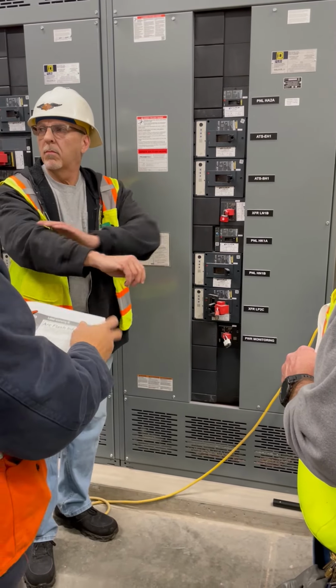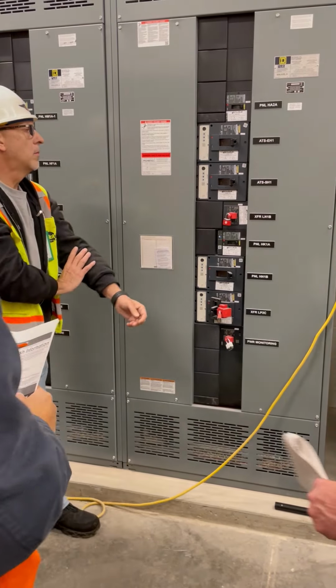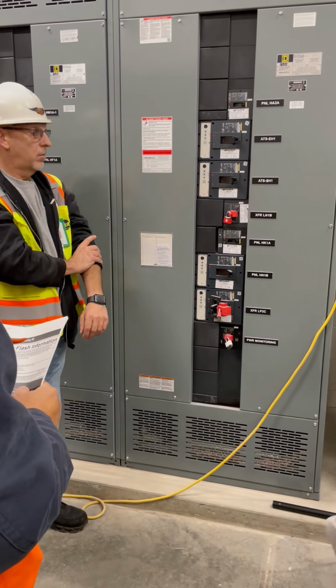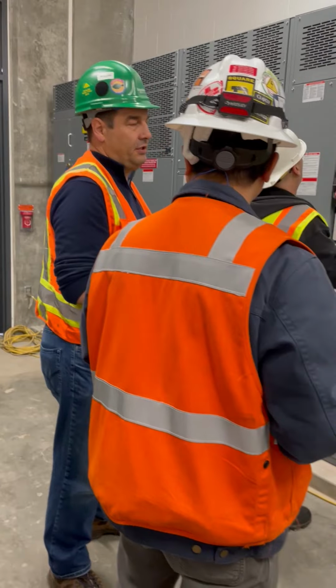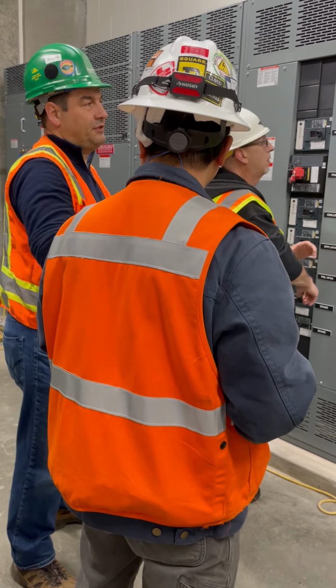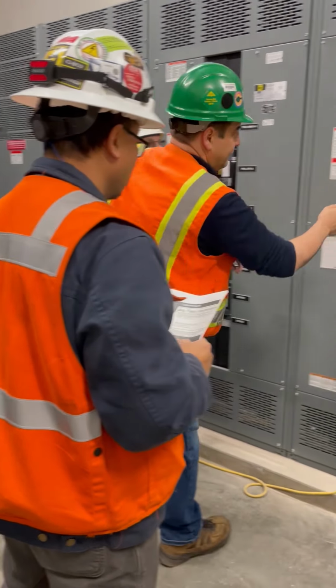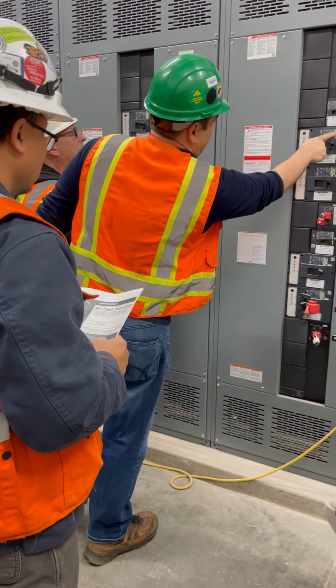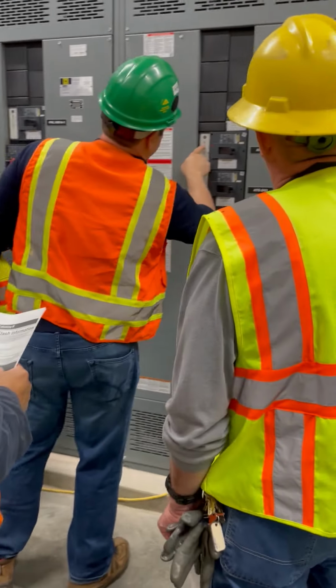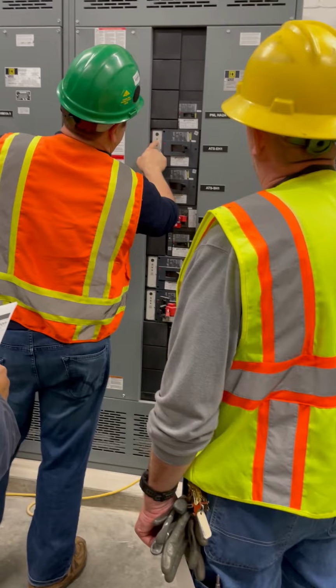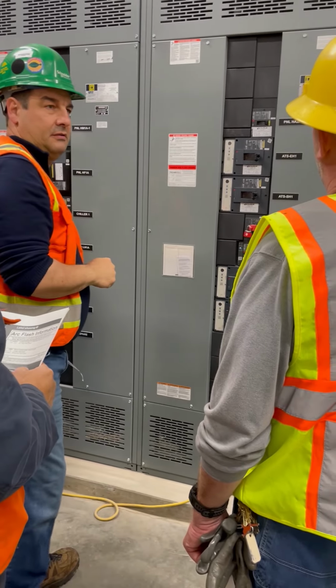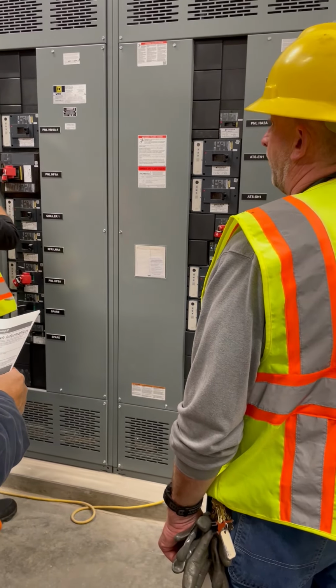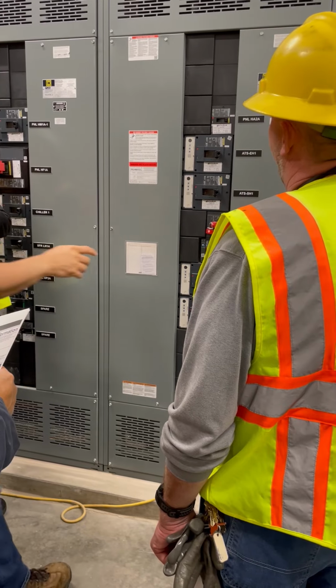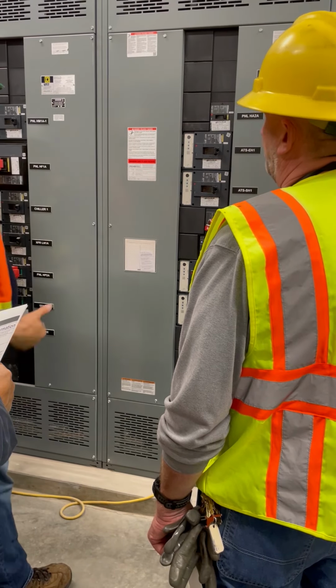Also, one thing to add to the settings, since we're looking at it, very important. The first setting is the long time pickup. If it's not set correctly, that could be the cause of a nuisance trip. I say nuisance trip because, for instance, this one right here is a 400 amp breaker, right? But it's actually set at 200, so it's like a 200 amp breaker right now. Now, if that's what the coordination study calls for, then it's correct, but if not, that's a 200 amp breaker, not a 400 amp breaker.